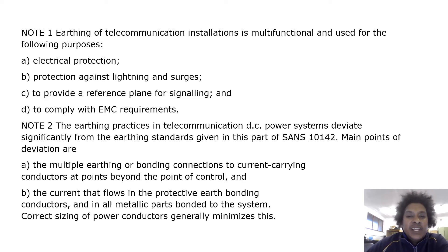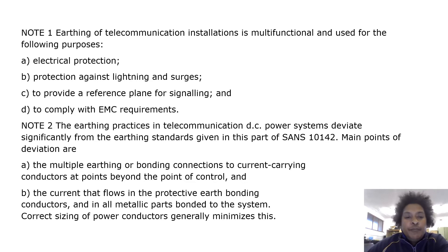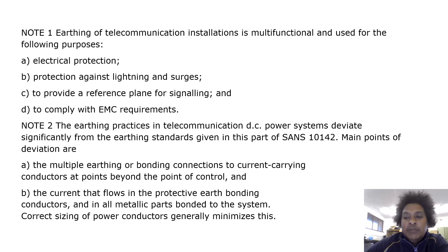Note: Earthing of telecommunication installations is multifunctional and used for electrical protection, protection against lightning surges, to provide a reference plane for signalling, and to comply with EMC requirements. Note: Earthing practices in telecommunication DC power systems deviate significantly from the earthing standards in this part of SANS 10142. Main points of deviation are the multiple earthing or bonding connections to current-carrying conductors at points beyond the point of control, and the current that flows in the protective earth bonding conductors and metallic parts bonded to the system. Correct sizing of power conductors generally minimizes this.